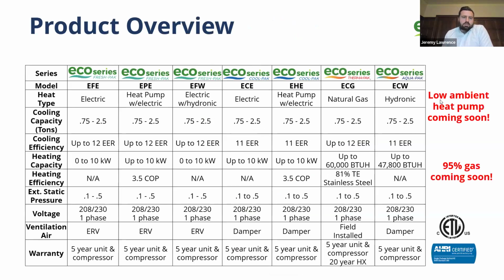These are the Eco Series units. What you see is they come in electric heat with air conditioning. This is the full line, I should say: fresh pack with the ERVs, cool pack with electric heat pump, and aqua pack with hydronic heat, which is the same as the electric heat unit, but there is just a separate hot water coil stuck right on top of the unit, either 2 or 3 row coils, depending on the capacity required. So that's it.